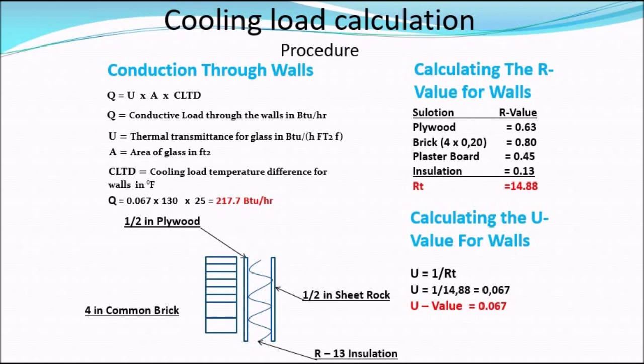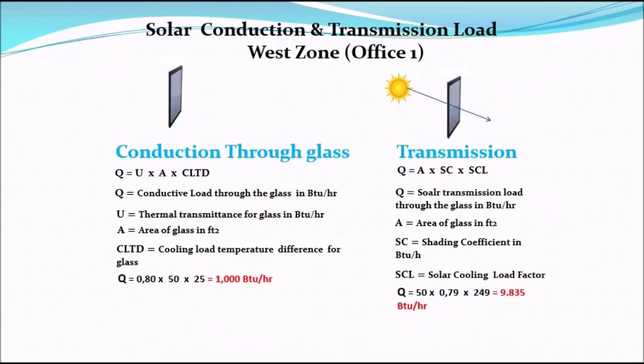Now let's calculate the conduction load through the glass. We use the same formula: Q = U × A × CLTD, where Q is the conductive load through the glass, U is the thermal transmittance for glass, A is the area of glass in square feet, and CLTD is the cooling load temperature difference for glass. Plugging in the numbers gives a total conduction load of 1000 BTU/hr through our glass.